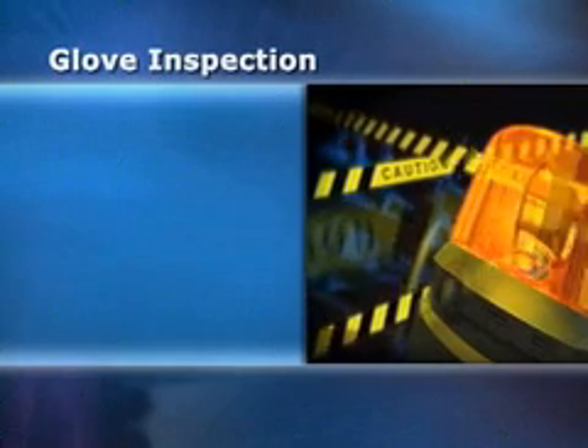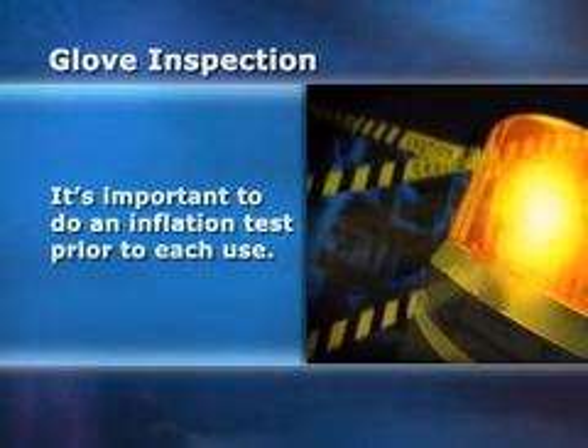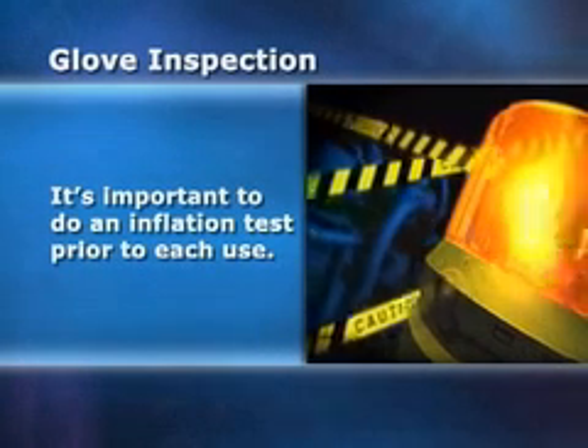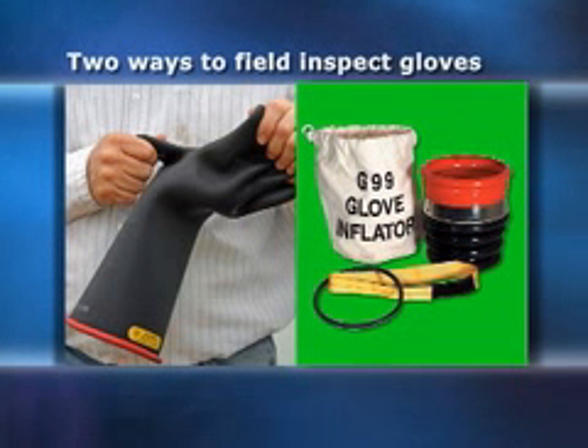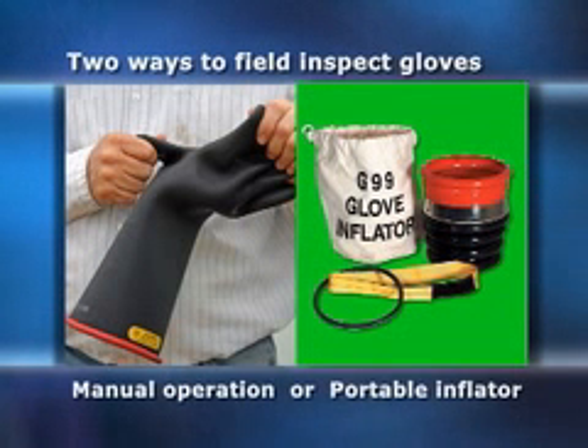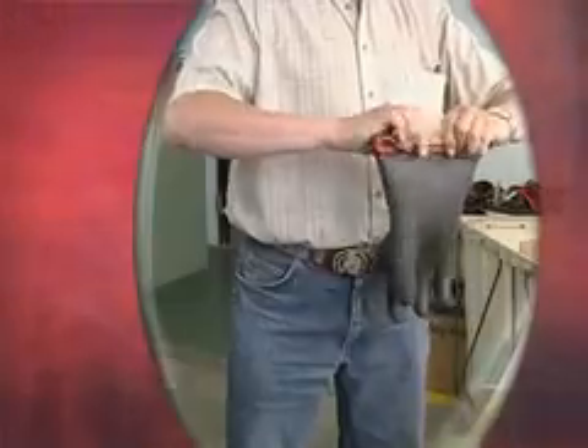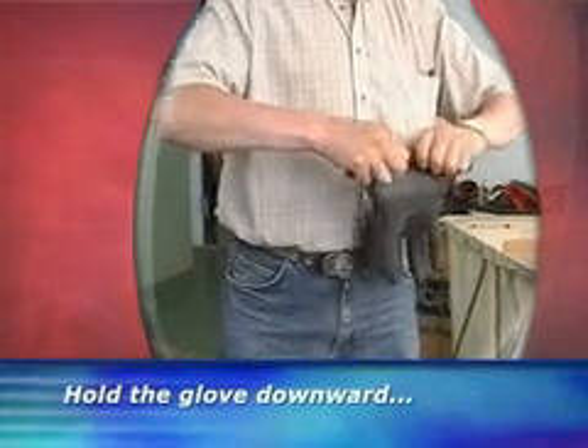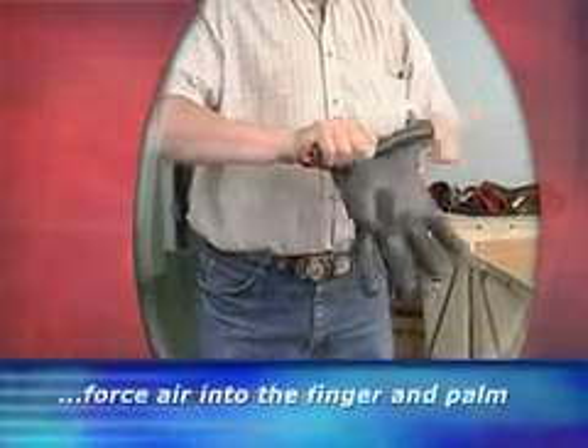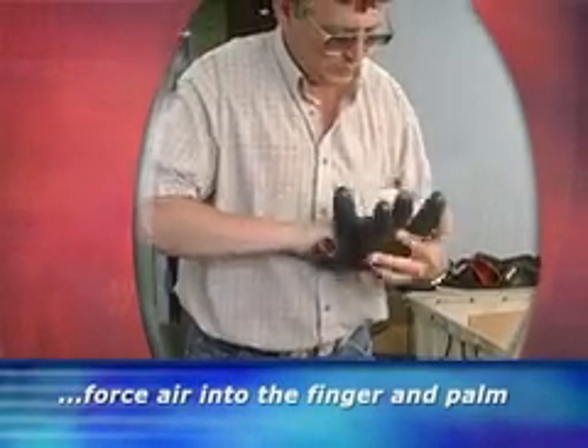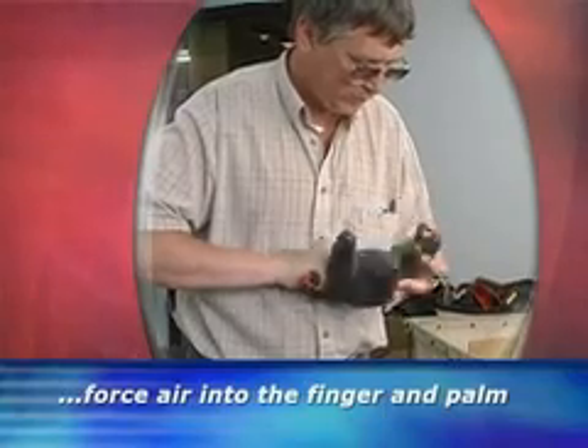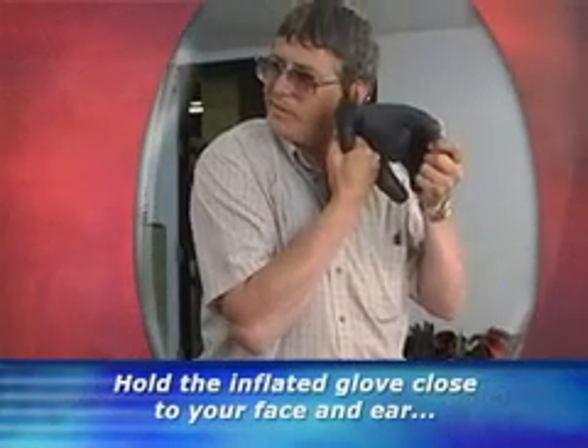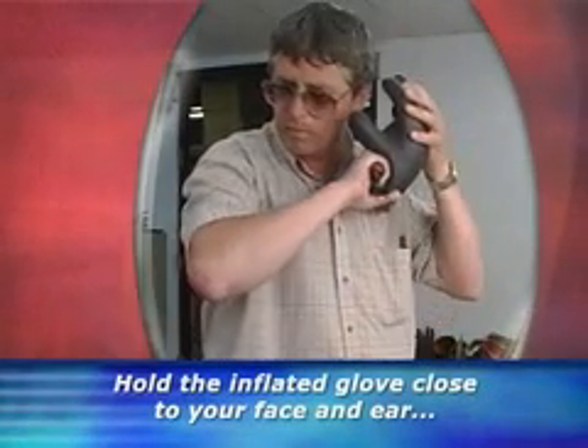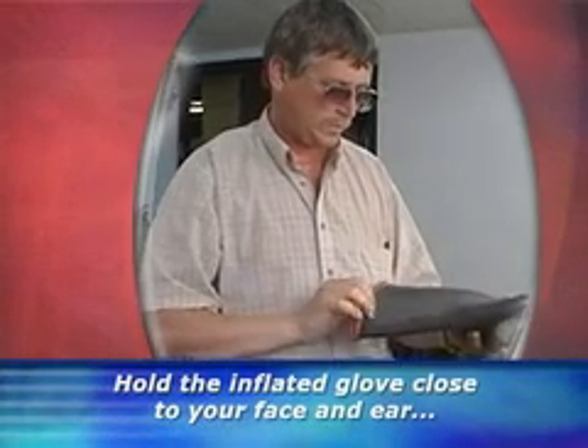To properly inspect the gloves, it's important to do an inflation test prior to each use. There are two ways to inflate gloves: through a manual operation or a portable glove inflator. To manually inflate the glove, hold the glove downward and grasp the cuff. Roll the cuff tightly to force air into the finger and palm area of the glove. Hold the inflated glove close to your face and ear to listen or feel for any air escaping from holes.